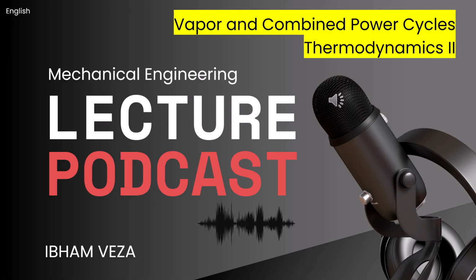It is clever. And regeneration has other big benefits, too. It helps to de-aerate the feed water, removing dissolved gases like oxygen that can cause corrosion in the boiler tubes. Okay, that's important for maintenance. Very. And it also helps control the steam flow rate. At the low pressure end of the turbine, the steam volume becomes enormous. Bleeding some off actually makes designing the final turbine stages a bit easier. Multiple benefits then. Efficiency, de-aeration, flow control.